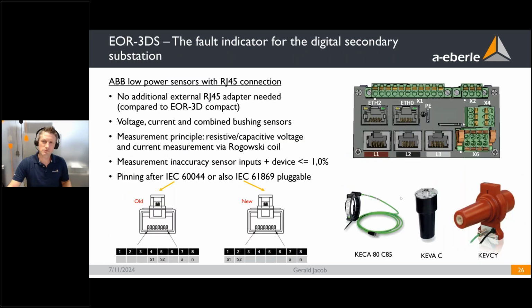Only 2 pages for the sensors of ABB and Siemens, because ABB has had these bushings with integrated sensors and the single sensors on the market for a long time. And unfortunately, the standard changed and it changed the pinning of the connector. So at first, the current was on the pins 4 and 5, and now it's on 1 and 2. But you don't need to take this into account with our device, because we internally short-circuited 1 and 4 and 2 and 5, so you can use both variants of these sensors.